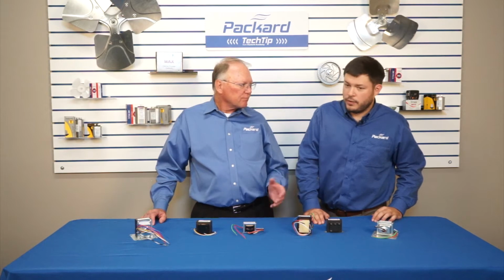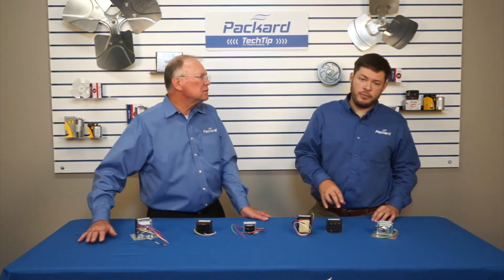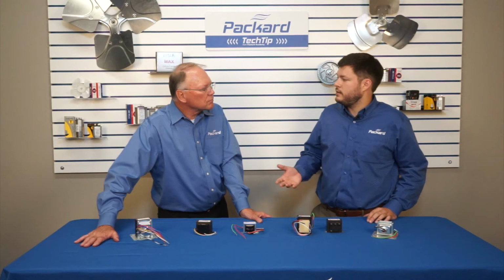Okay, all right. So how do I select one? Well, first you need to determine your source voltage. That's going to be your primary. And then the critical second feature is your secondary voltage, the voltage you need your transformer to create. The third part of that is always going to be your VA rating. Your VA rating is a capacity. It's quite literally volts times amps.